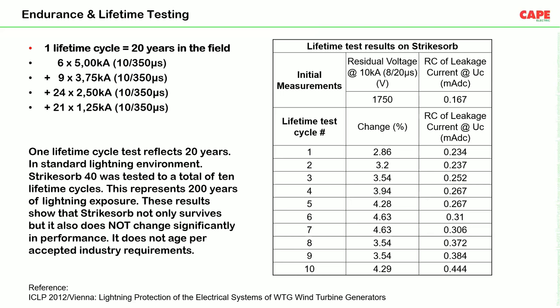So on the right side, you can see a table. What was the outcome of the result when we did this testing on Strikesorb 40? The residual voltage, that means the voltage protection level, you can see the change in percentage. After the first life cycle test, it was 2.8%, second 3.2%, and in the 10th test, the change was only 4.29%. In terms of leakage current, after the first lifetime test cycle, the leakage current was 0.234 milliamperes, and after the 10th life cycle test, the leakage current was only 0.444 milliamperes. So this is a very, very good test result in terms of operations and reliability.